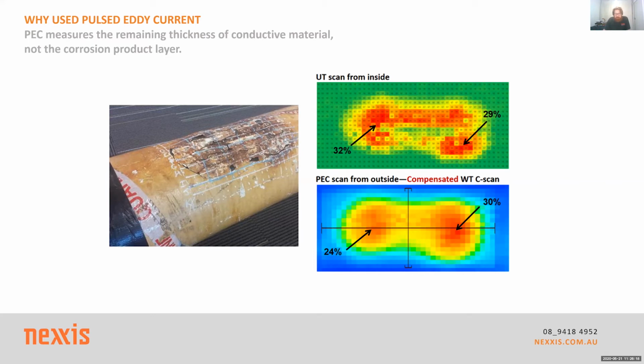The technique itself is designed for CUI, corrosion under insulation. The system generates an electromagnetic field, which creates eddy currents in a ferrous asset or sample, and then it quickly turns off, and we measure the decay, an impedance measure as the magnetic field is decaying. If you have a solid piece with no corrosion, you get a nice steady decay. When you get corrosion or wall loss, because there's less mass affected by the magnetic field, it dissipates a lot quicker, and you see a different shaped curve. That gives you the ability to identify corrosion with a reasonable level of accuracy.